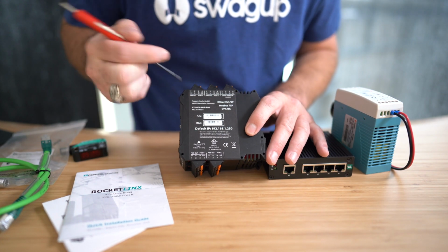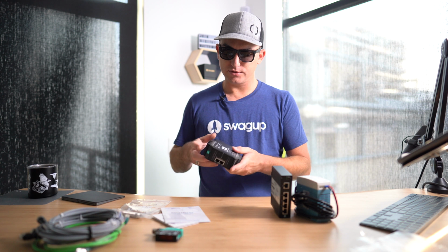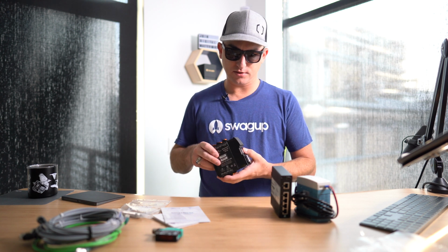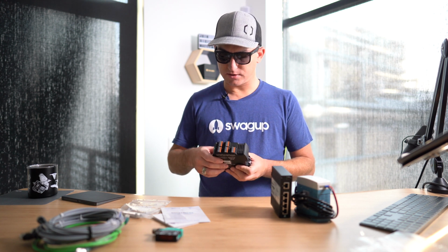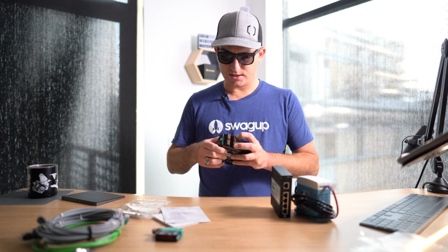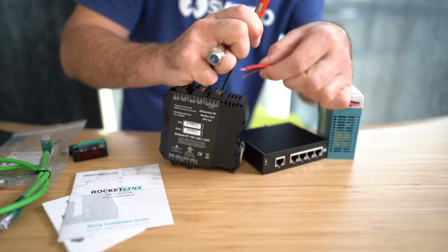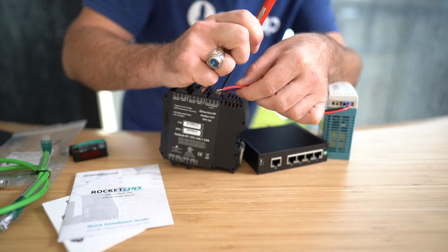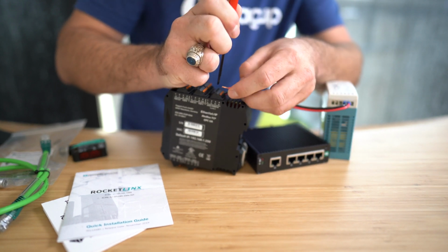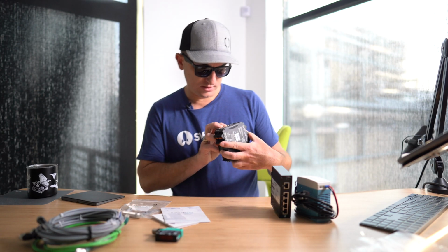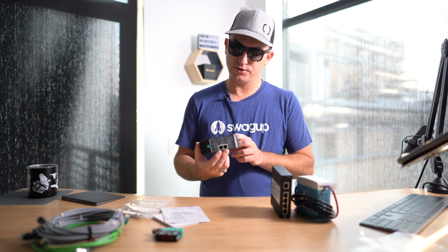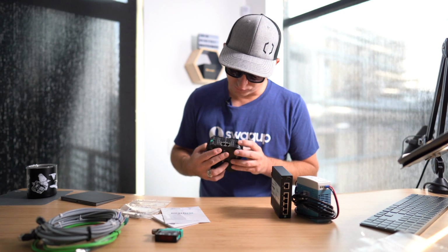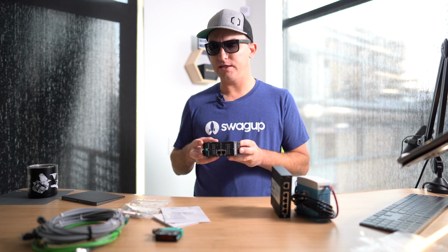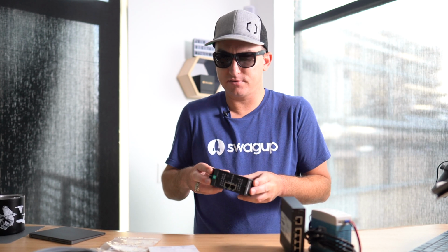pretty solid. It is a plastic build, but good news on that, it's going to keep the cost of this device low. And then these terminal blocks are the push-in type. Push that in with the screwdriver, plop the wire in. You got two Ethernet ports, Ethernet one, Ethernet two, so two main ports on there, and a total of 8 IO Link ports. You could hook up to 8 devices on here.